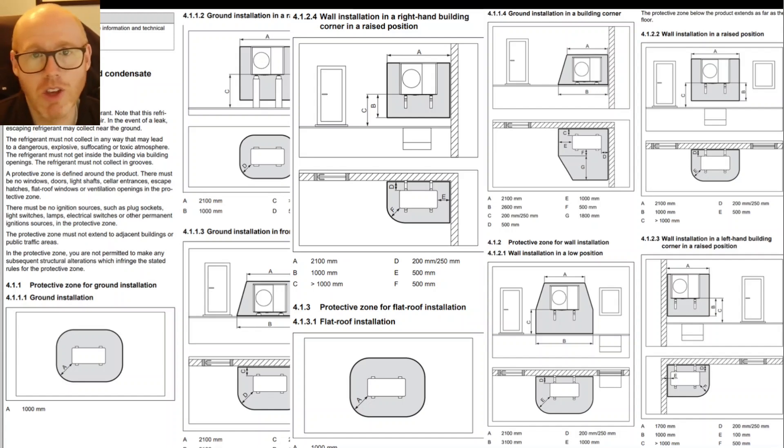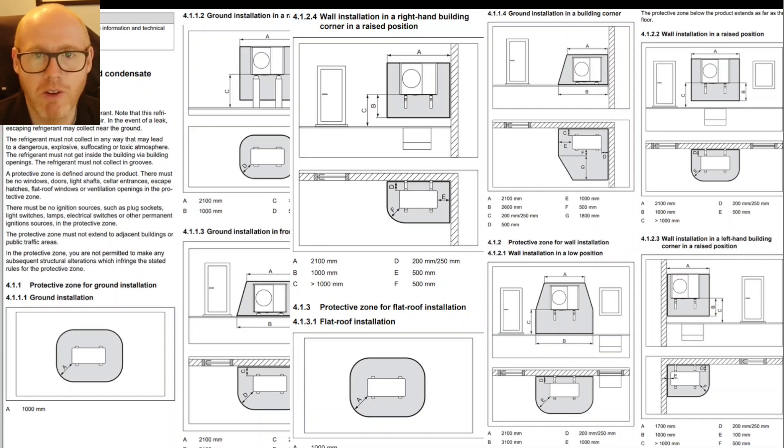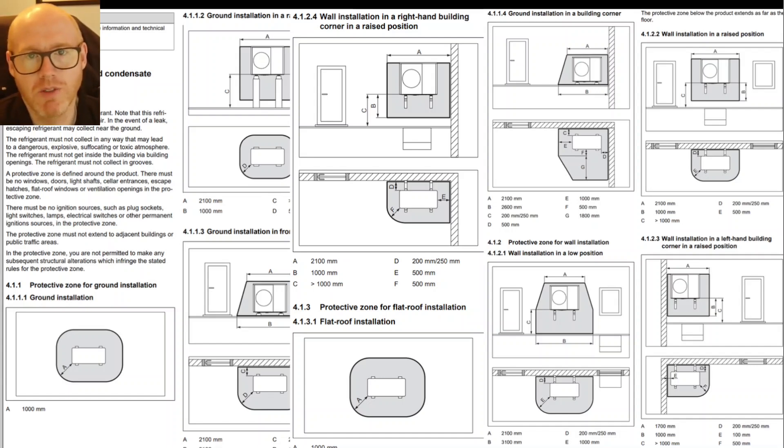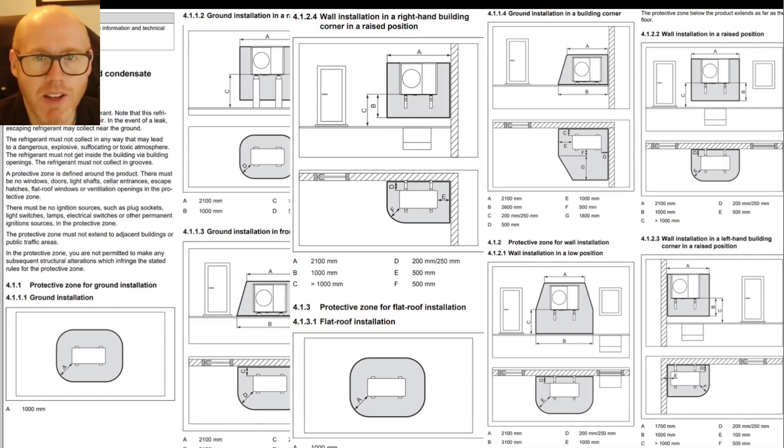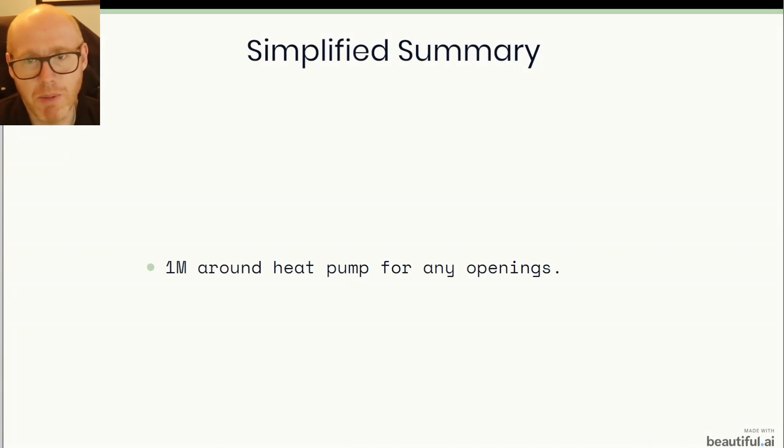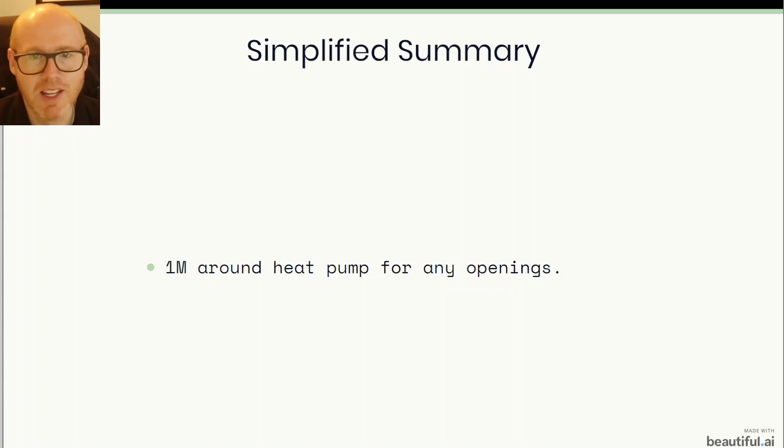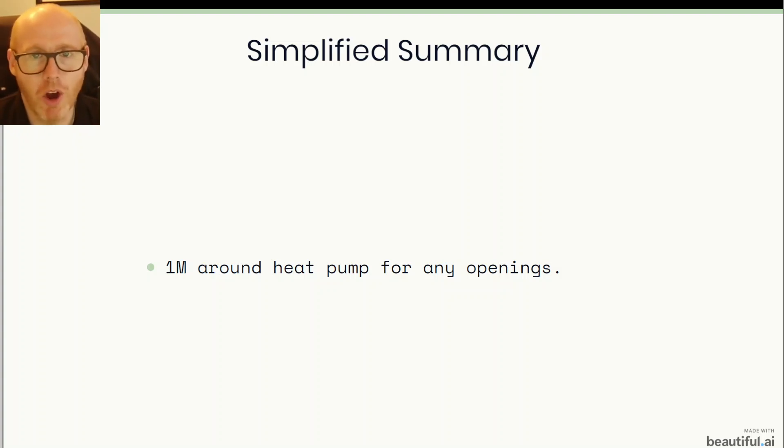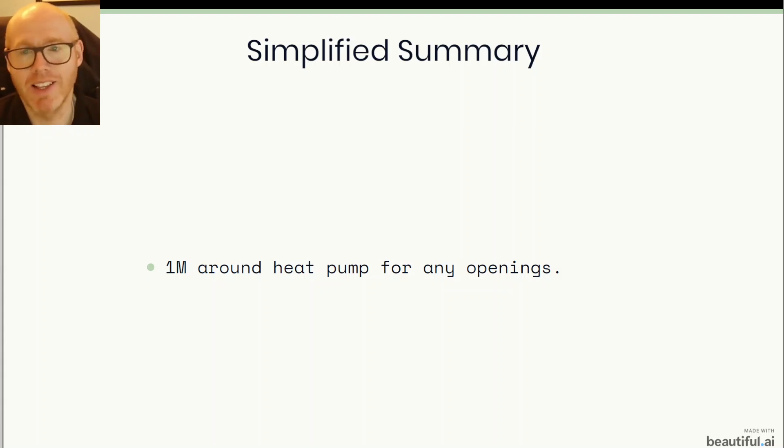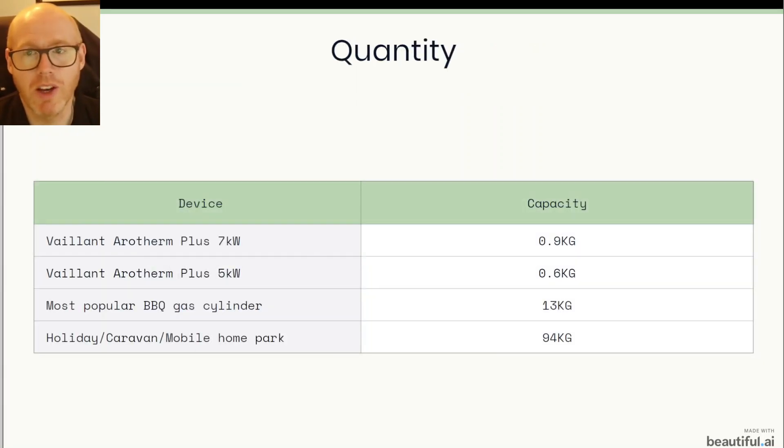We're trying to keep it a meter away from doors and a meter away from windows and before you know it, half of the UK becomes impractical to have a heat pump whatsoever because they can't put it anywhere. We hear over and over that the permitted development rights of heat pumps are going to be relaxed but that's been in the pipeline for well over a year so we'll see. This is a simplified summary and I know it's more nuanced than that but basically a meter around the heat pump for any of your openings and in a lot of cases this will also apply to air bricks and drainage and loads of other things as well so it's not just doors and windows that you need to be aware of.